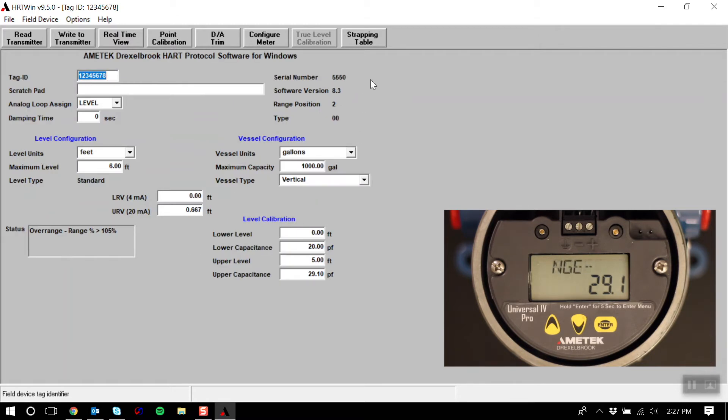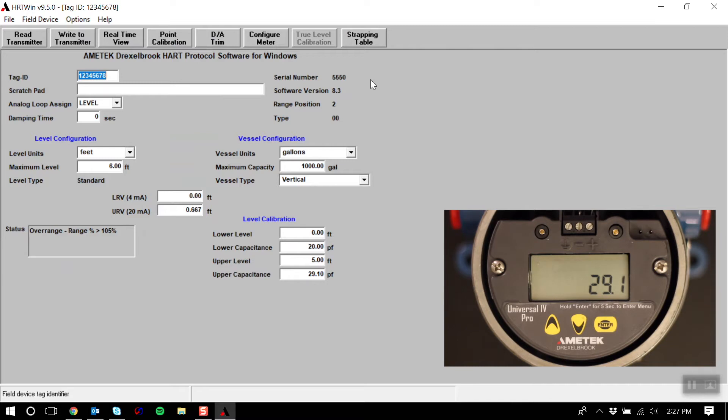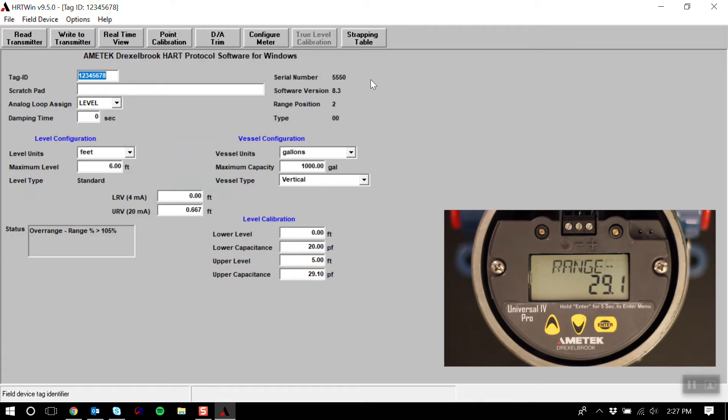Now as far as calibration goes, there are two types of calibration: point calibration and calibration using capacitance values. For point calibration, this can be used when the tank level can be moved or is known. When doing this, you will need to know the real-time level value while doing the calibration, and it requires two points to create a linear interpolation. This is done using the point calibration button.